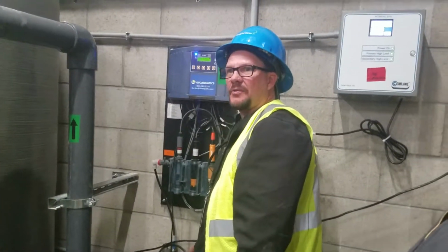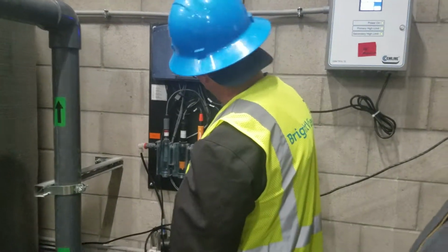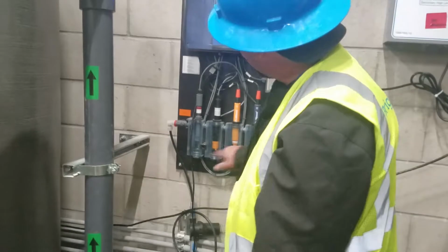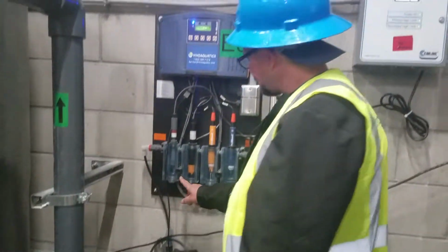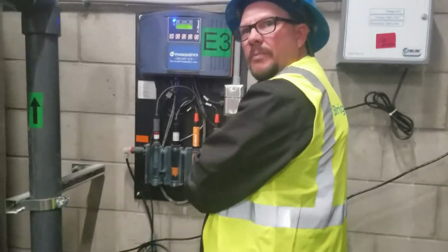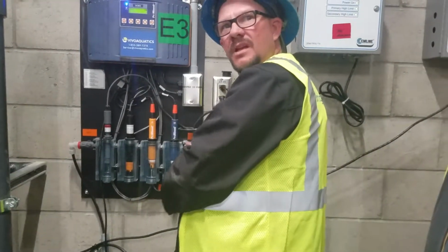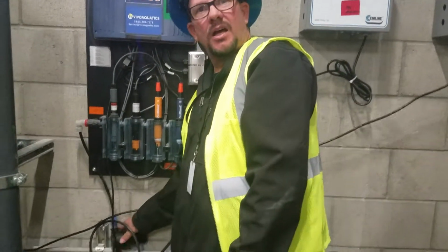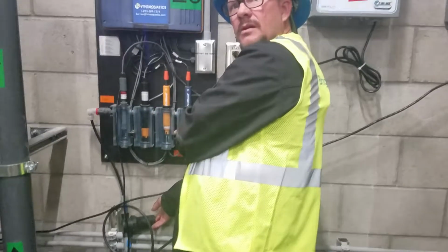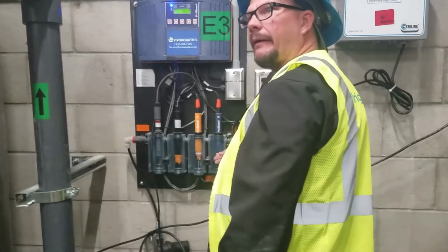Make darn sure that you're checking these, because if you get a flow issue at all, we like to crank these back just a little bit to get a little bit of a wobble or movement, not necessarily a spin. We'd like to get it to where it's not going to fail, but yet we're going to get a good sample. We don't want the water blowing through there. If you start getting a bunch of debris trapped in here, it's going to affect all this. So just keep in mind that you've got a lot of money tied up right here.